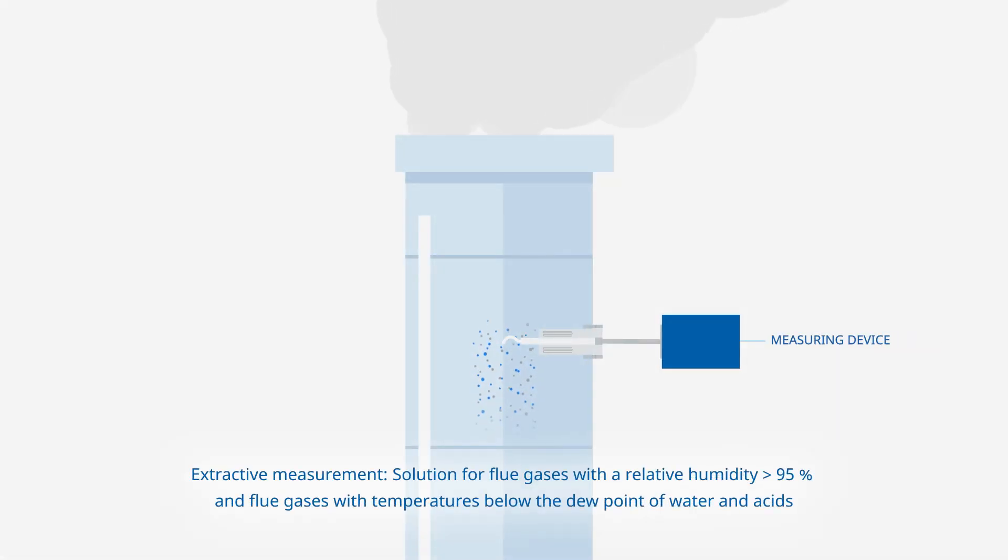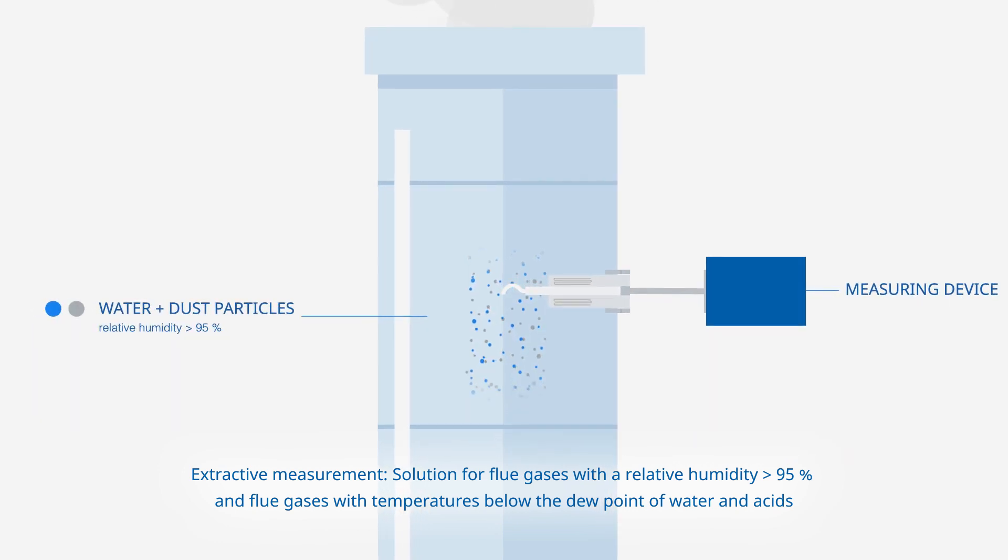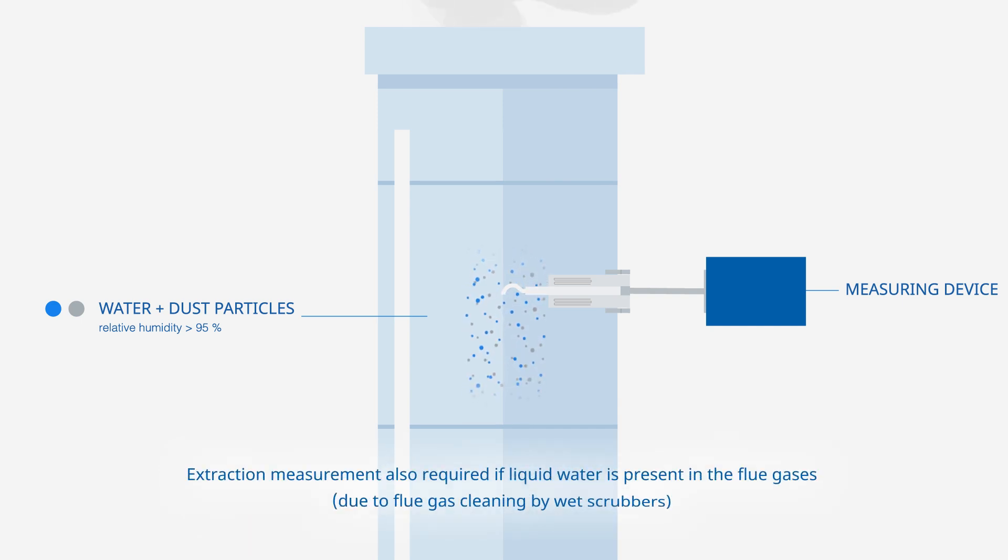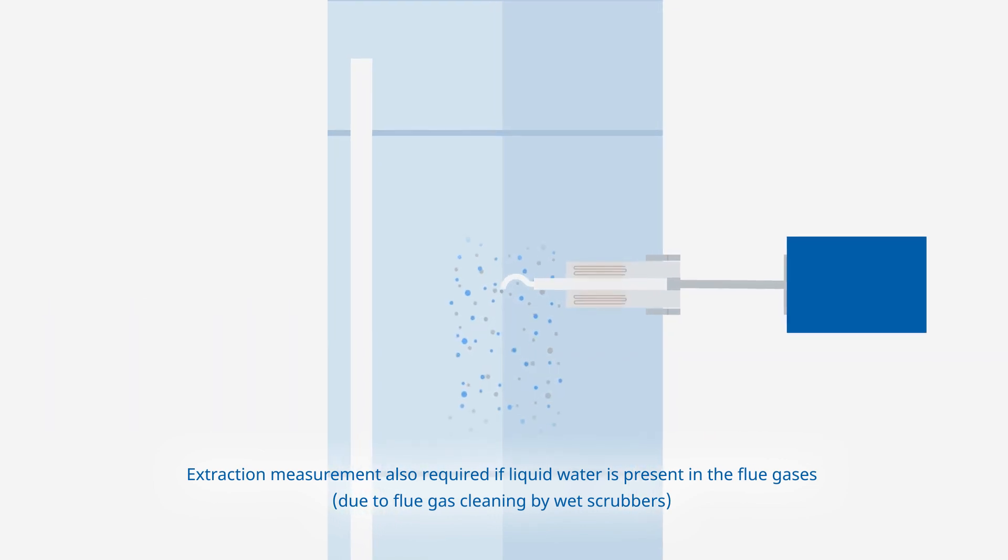Extractive measurement is the solution for flue gases with a relative humidity higher than 95% and flue gases with temperatures below the dew point of water and acids. Extraction measurement is also required if liquid water is present in the flue gases due to flue gas cleaning by wet scrubbers.